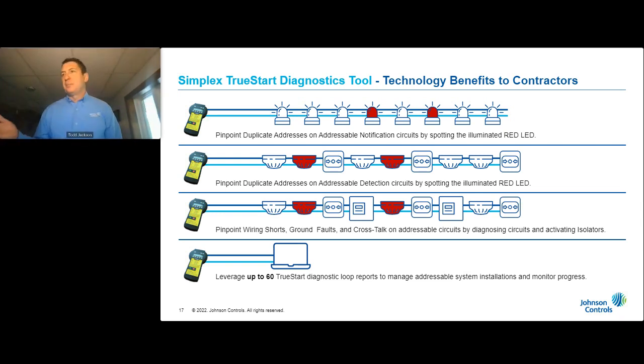Our tool does a couple things. First, it stores all the testing, which is really cool because then you can plug it into your laptop and print off the results of a test once you've corrected any of the field faults. You can show those test results, literally treat it like a submittal, and send it into your GC and say the wiring plant on floor 3, branch 2 is complete. Here's evidence that it's properly installed and clean.